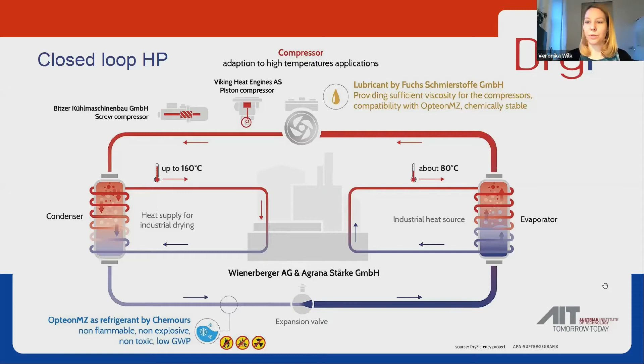Now I'd like to move to the slide about starch drying. Here you see how we integrated the heat pump into the starch drying of Agrana. It's a flow stream dryer where the wet product is fed as a solution into the dryer, dispersed there, with a stream of hot air coming in where particles are dried and conveyed within the dryer. Then the dry product is separated from the airstream, and exhaust gas leaves the dryer. They typically use 200 tons per hour of drying air with an inlet temperature of 58 degrees C.